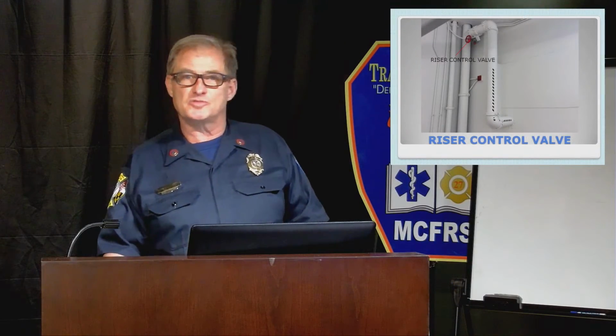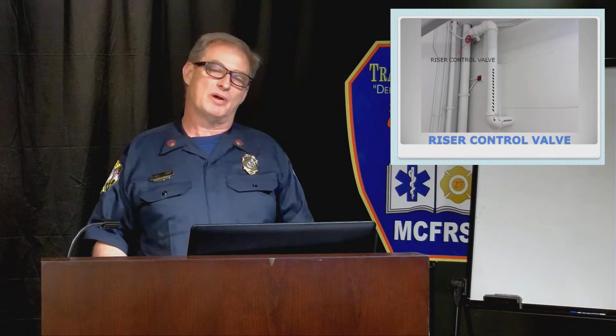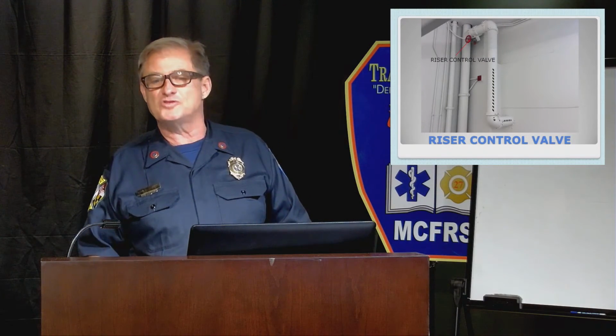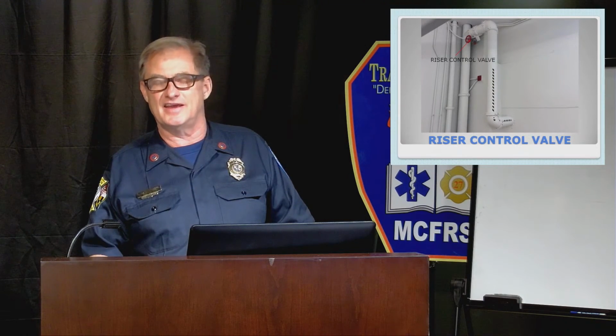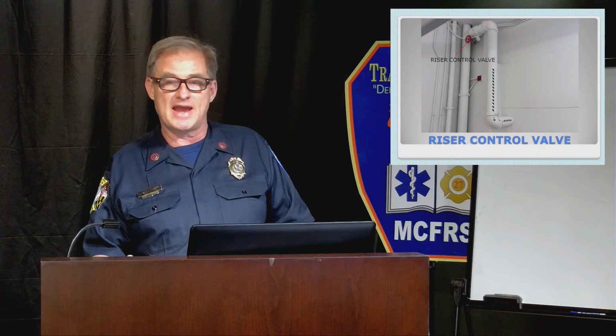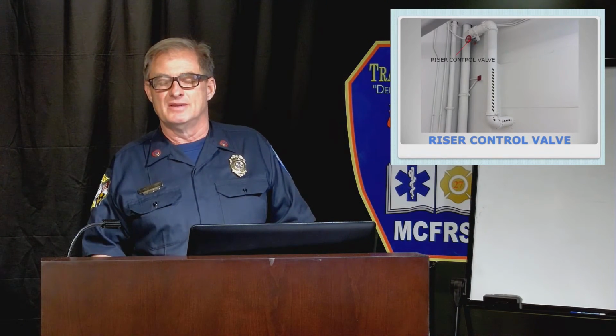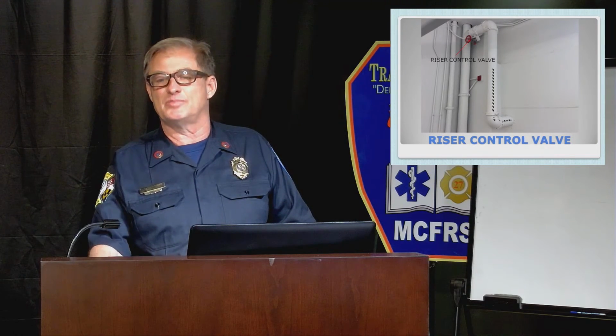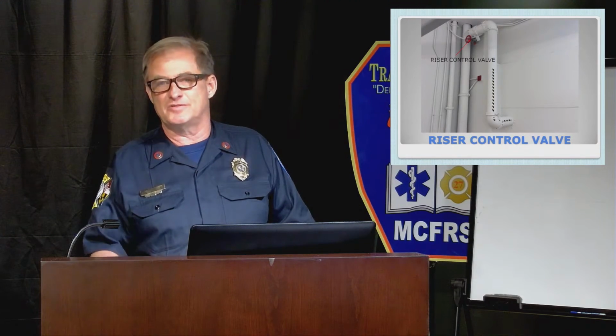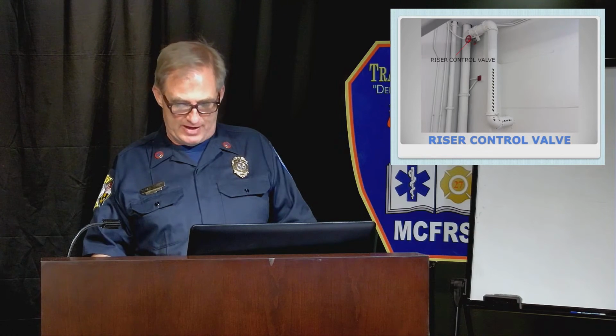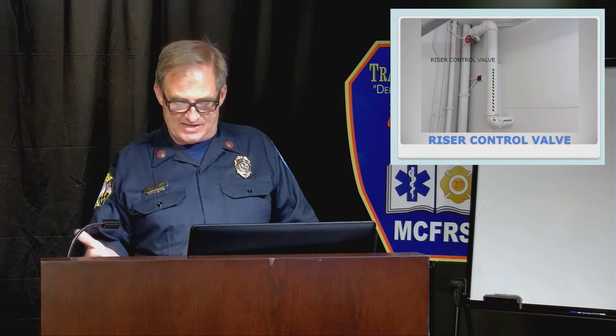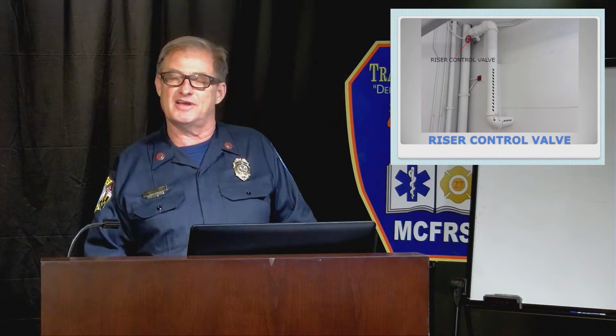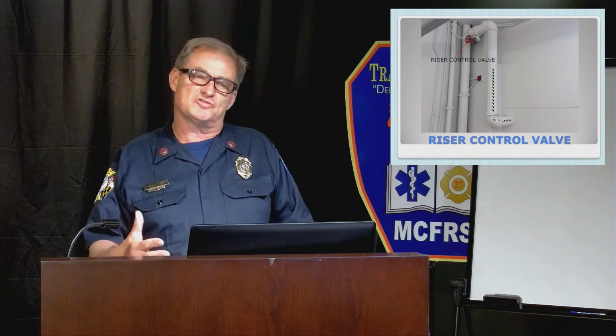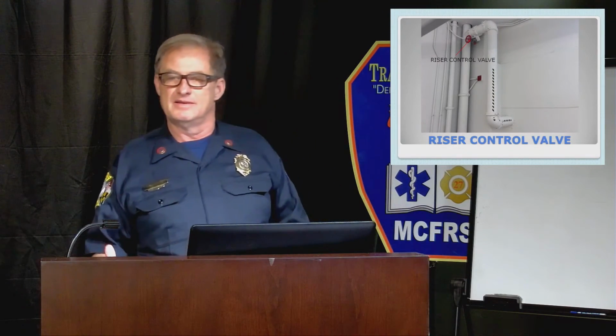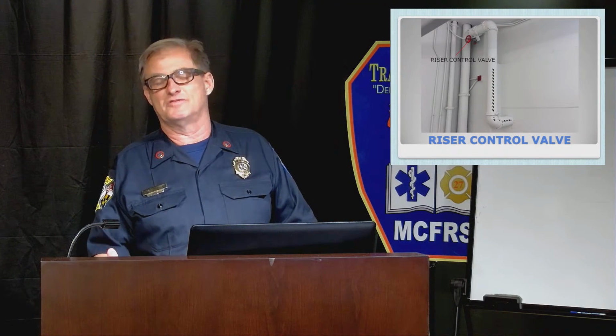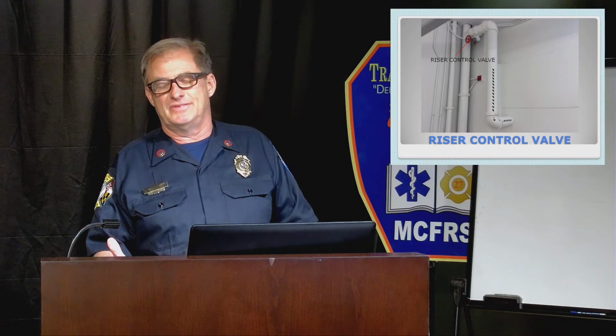Why did this happen? I know there's been discussion by some that maybe the pumper operator overcharged the system. Well, I can tell you definitively that is not the case. The fittings that came apart are rated for a working pressure of 300 psi. Well, when you say working pressure of 300 psi, they're probably tested to a pressure of 500 or 600 psi. I know the new pumper that Wheaton's buying meets NFPA specs, and the maximum we're going to pump at is what, 250 psi at 50% of the rated capacity of the pumper, right? So if we have a street pressure, maybe best case scenario of 100 psi, maybe we can pump this thing at 350 and push 400 psi, but not realistically.